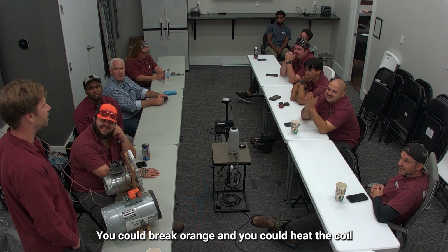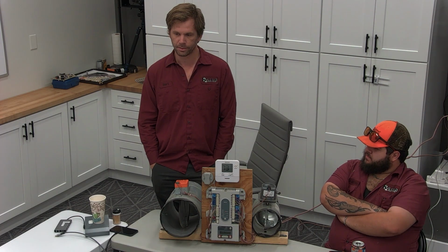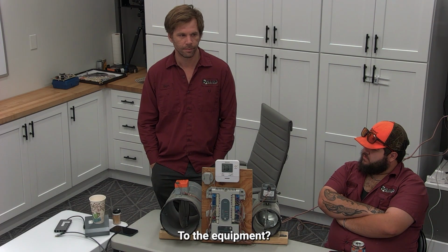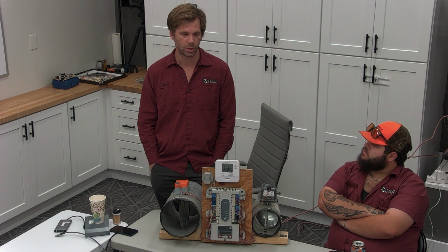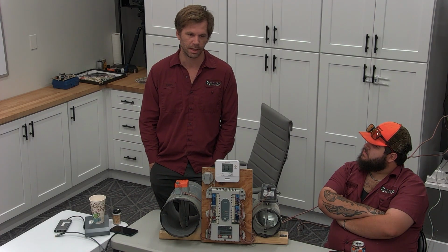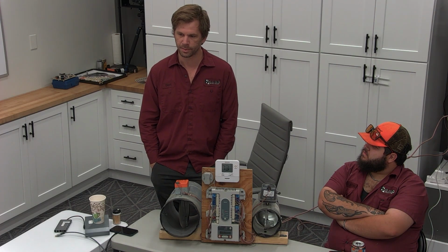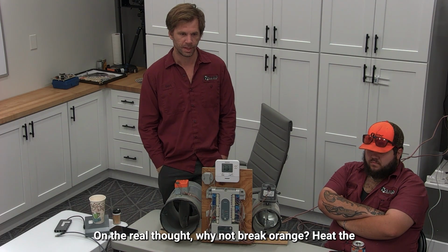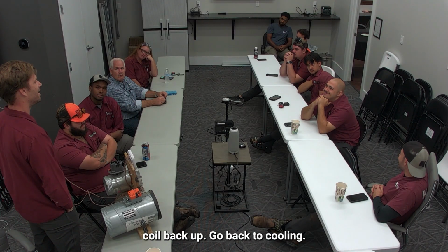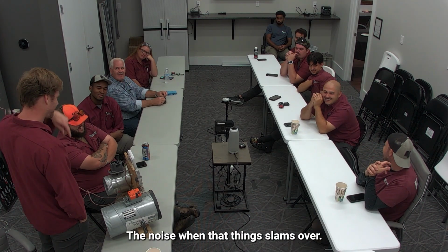Resistance. You can break orange and heat the coil back up. It is red. I'm trying to think of, last time I did this was in Legends for a guy that keeps it really cold upstairs. And it was red, it broke red. To the equipment? To the equipment, yeah. If you break red to the equipment, you're not resetting your thermostats because it's on a different power. On a real note, why not break orange? Heat the coil back up. Let's go back to cooling. Such a really terrible idea. So great noise when that thing slams.